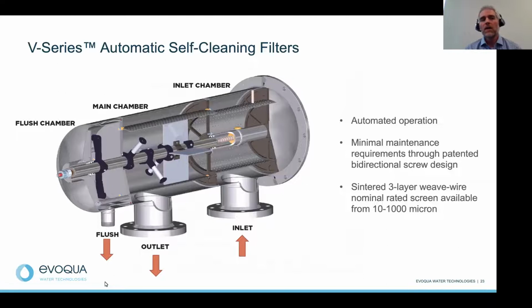Let's talk about how this technology works. Again, as I mentioned earlier, it's a fully automated operation. No additional external drives or gearboxes are required. It's really minimal maintenance requirements through its patented bidirectional screw design. So how this works: water flows from the inlet on the bottom right flange, comes into a pre-screen, really kind of protecting the internal mechanism. Basically, it eliminates any types of large debris left over from any type of construction, right? Wrenches, rags, Snicker bar wrappers, as Gary mentioned, right? Really to protect the internal mechanism of the filter.